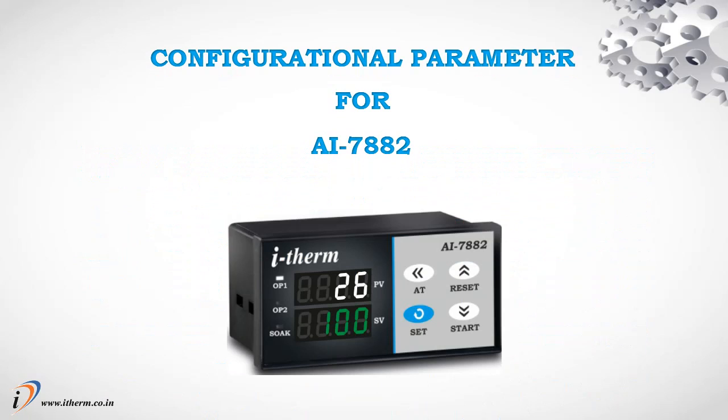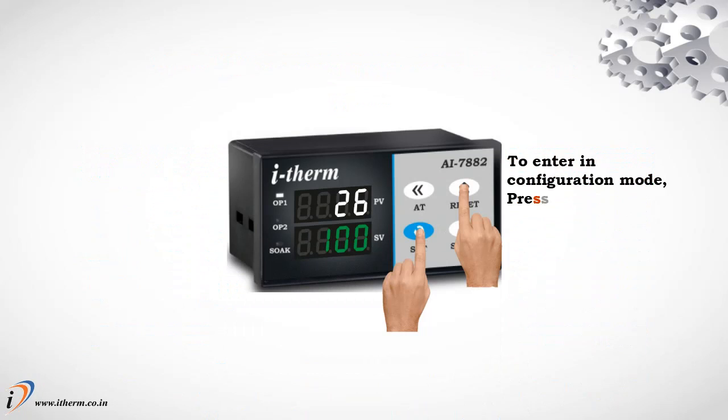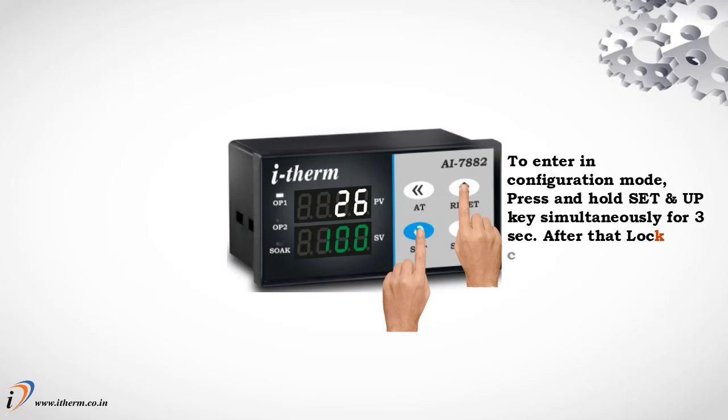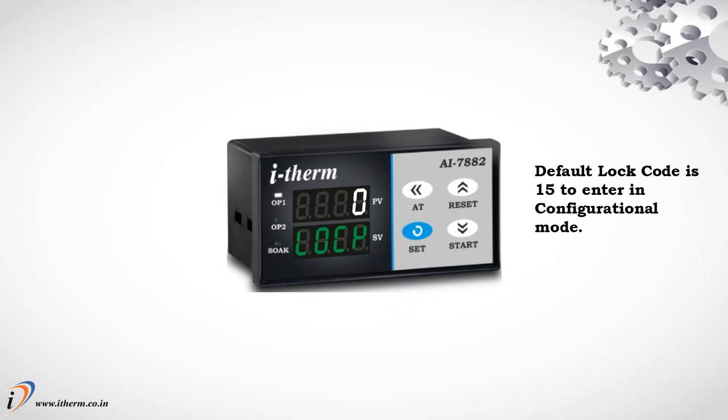Configurational parameter for AI7882. To enter configuration mode, press and hold the Set and Up keys simultaneously for 3 seconds. After that, the lock code will appear. The default lock code is 15 to enter configurational mode.